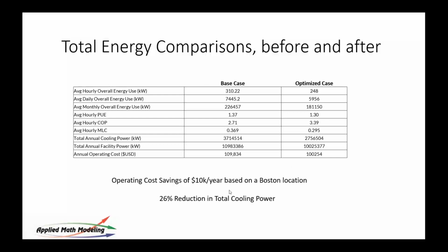So about $10,000. We didn't do mechanical optimization here. We simply did white space optimization. What we have found in the work that we've done is that mechanical optimization can gain you a whole bunch of savings. And this is not unusual. This represents about 26% reduction in total cooling power from managing the white space by itself. So that's a fairly good representation.